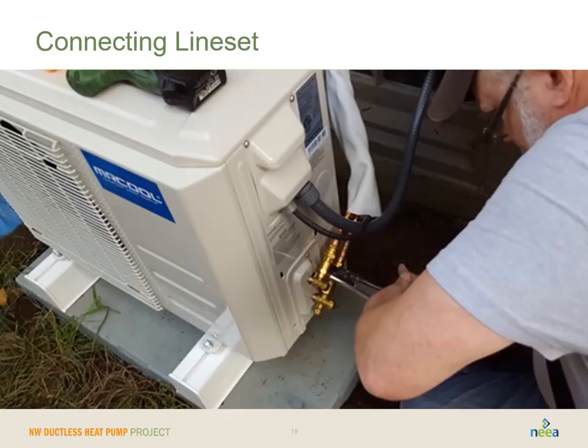Connecting the line set. This is where that torque wrench is going to come in handy, and you're going to connect it at both the compressor on the exterior and on the indoor head. One of the challenges here is getting that insulation just right. And we'll talk a little bit more, but the insulation around these line sets, try not to cut it off too much. It's better to scrunch it back when you make your connection so that it flexes and covers this entire line.